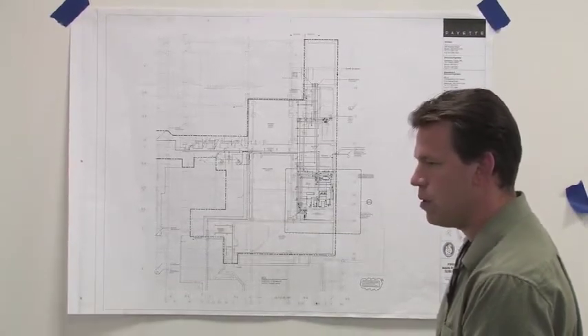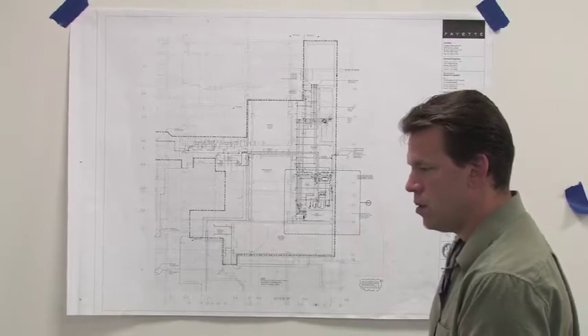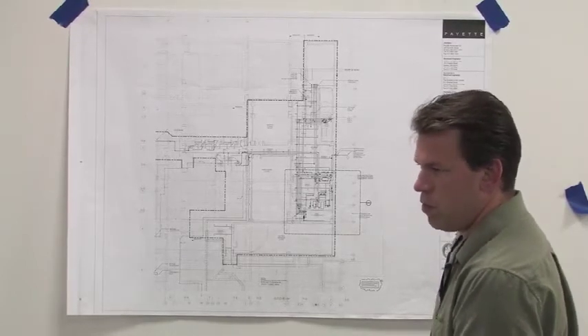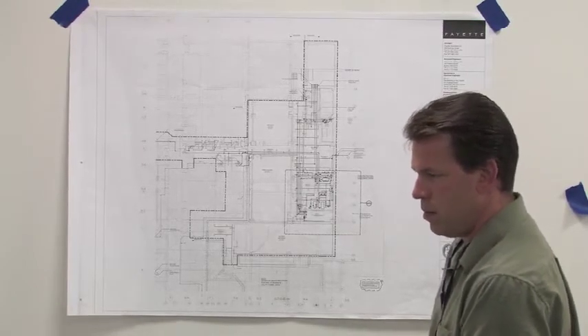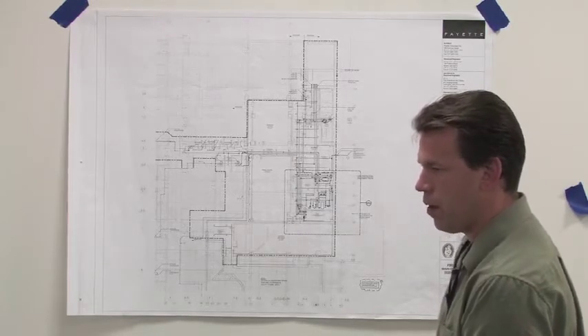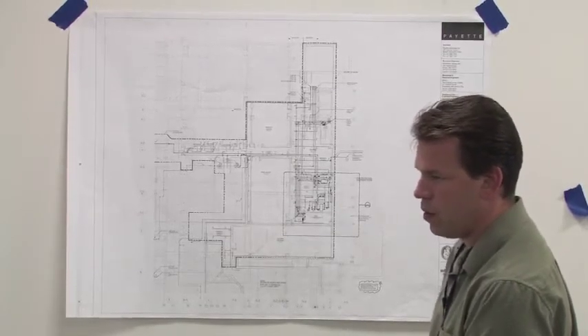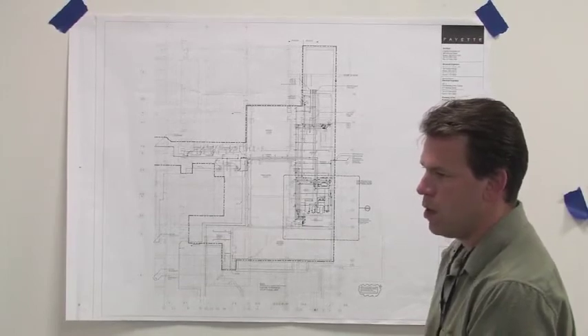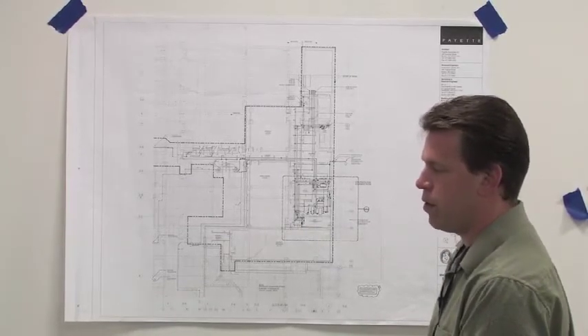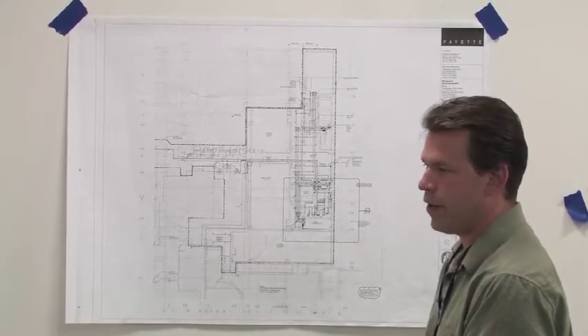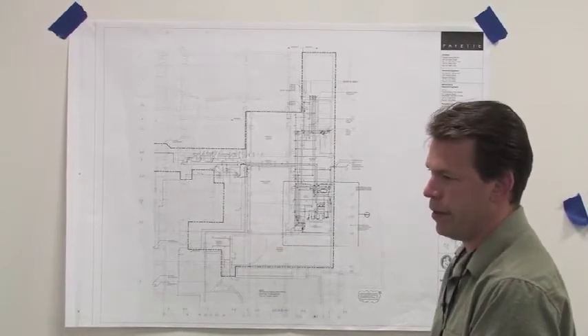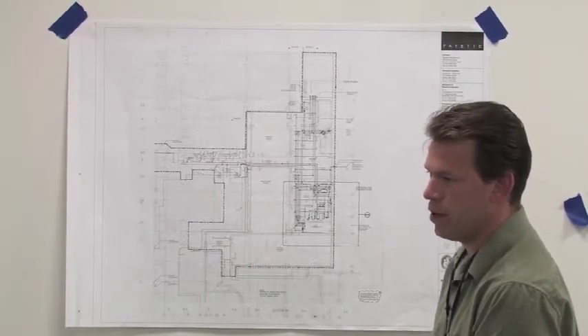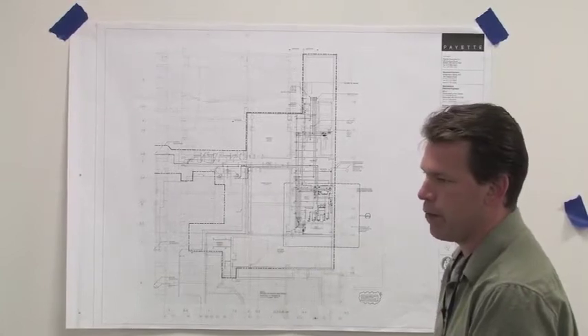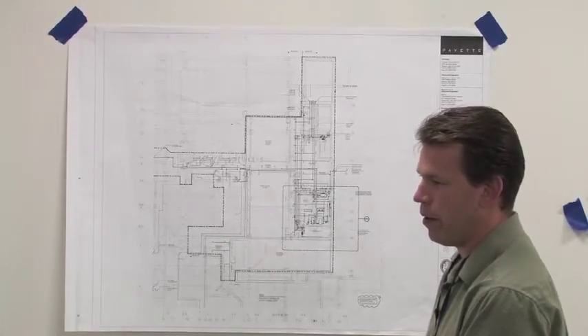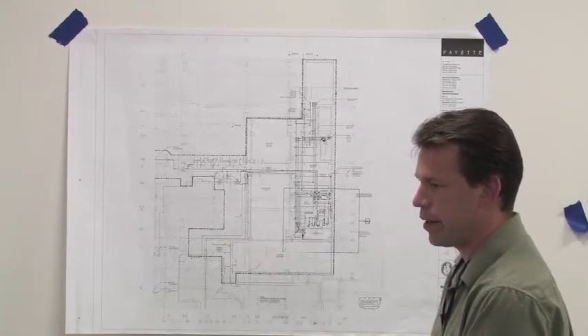So the fire pump, that's something different than we haven't seen, right? Yeah. So there are 2 separate connection points out there? 2 separate connections, one for low zone, one for high zone. Is that for the fire department to know what pressure they're going to put? They'll be labeled. Yeah. So there are no valves that could fail between the fire department connection and the sprinklers, essentially. There's nothing that's going to be closed, like a PRV or anything, in the way of that water if they need to connect and need the water.